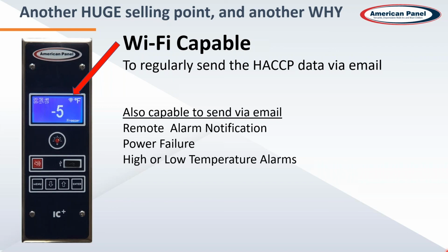The high and low temperature alarms, like we talked about, again, emailed out. Also, door open too long. That is an email notification option. You can have that going to the kitchen manager. If they're back there and they're leaving the door open while they're loading for too long, email can blast to your kitchen manager and say, hey, somebody needs to go shut the walk-in door.